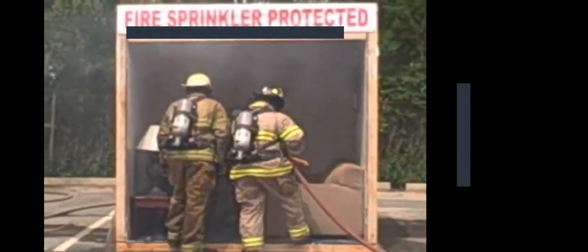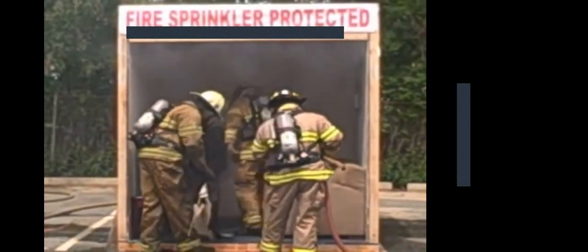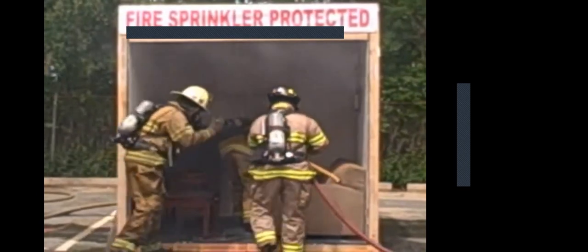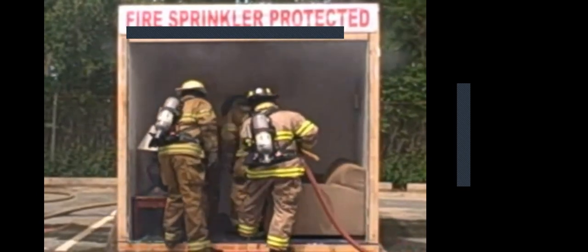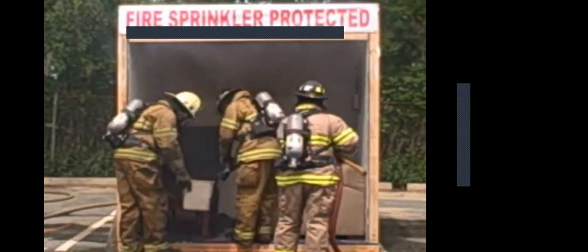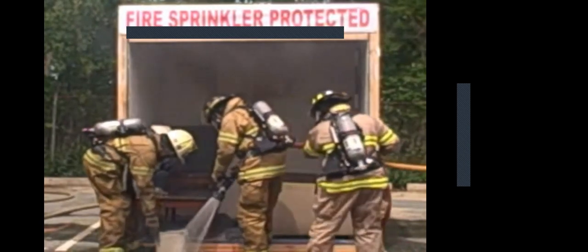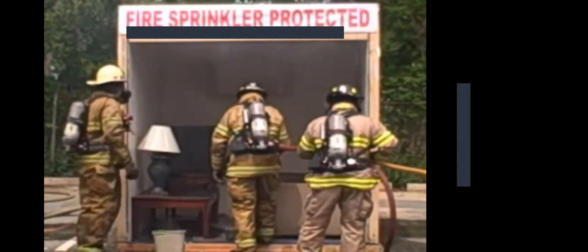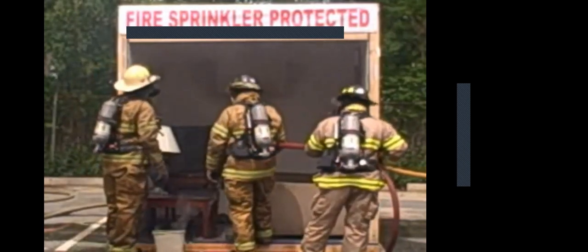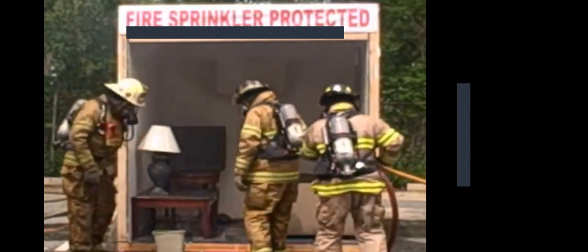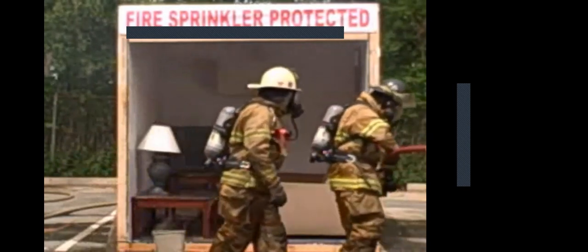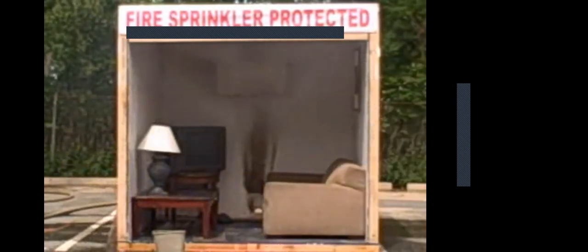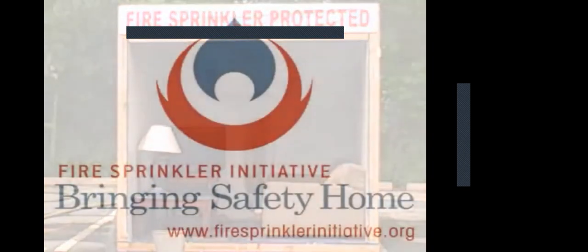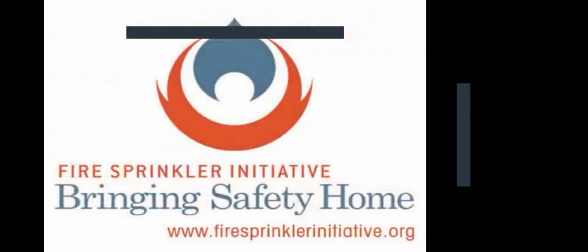Okay, now what happened here is when the temperature in that room got up to about 135 degrees, it activated the sprinkler. Now, in 90% of the cases, only one sprinkler head goes off. So, yes, there is a bit of water damage, but the water damage that a single sprinkler head causes, compared to the kind of damage you'd have going into a blazing room like this with fire hoses, is minimal.